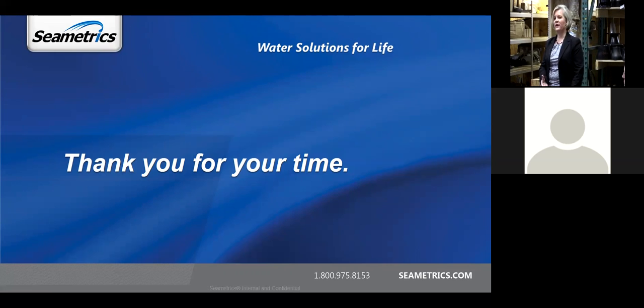I know in the irrigation market you guys want durable, long-lasting, and we didn't want to have any bumps in the road. So we took our iMag and scaled some of the features out of the base meter to get it down to the price point that the irrigation market will bear. You guys don't typically need things like HART protocol and 4 to 20 milliamp. You can add them onto this one and get that P version I showed. But for this base meter, it's rate, total, pulse, and then the next most common thing is data logging.